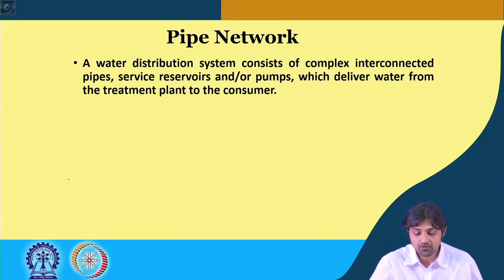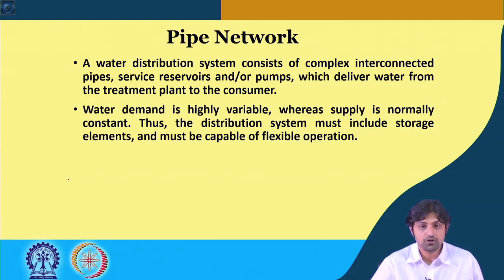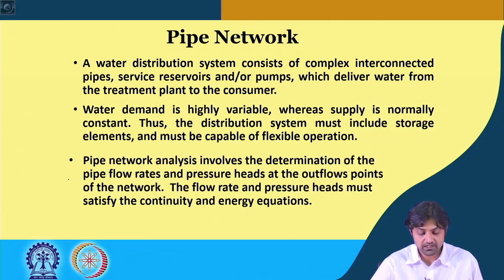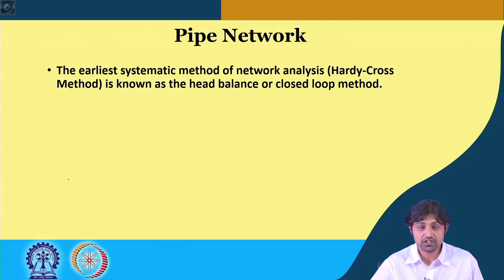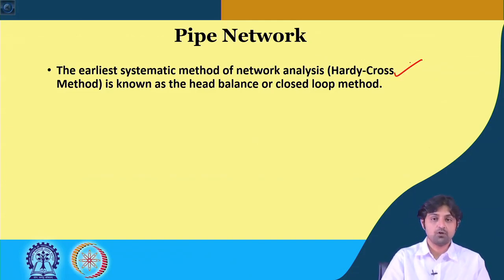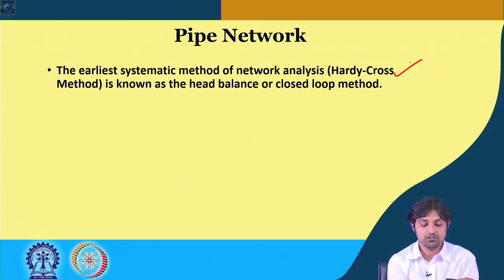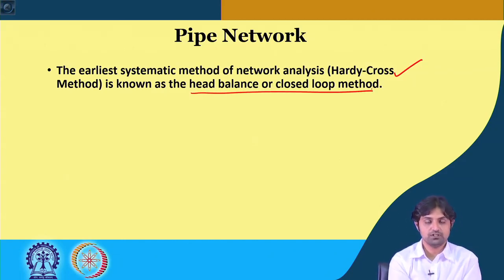A water distribution system consists of complex interconnected pipes, service reservoirs, and pumps that deliver water from the treatment plant to the consumer. Water demand is highly variable while supply is normally constant, so the system must include storage and be capable of flexible operation. Pipe network analysis involves determining pipe flow rates and pressure heads at outflow points, satisfying both continuity and energy equations. The earliest systematic method is called the Hardy Cross method, also known as the head balance or closed loop method.